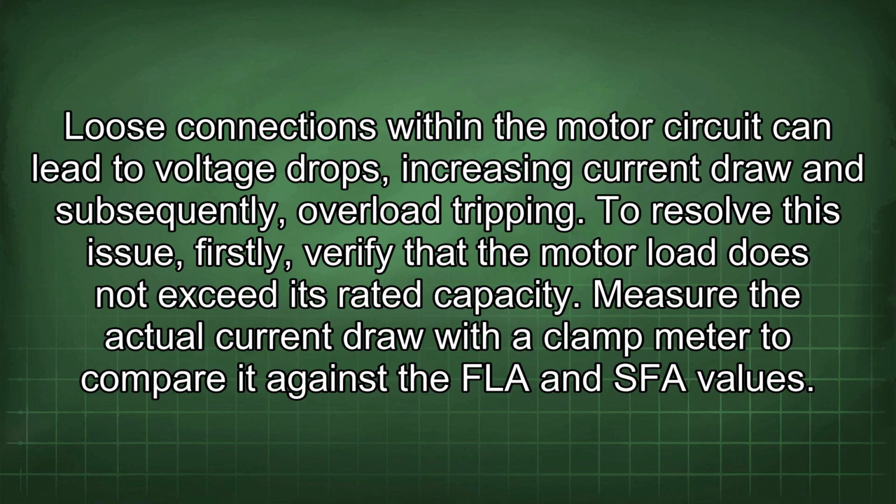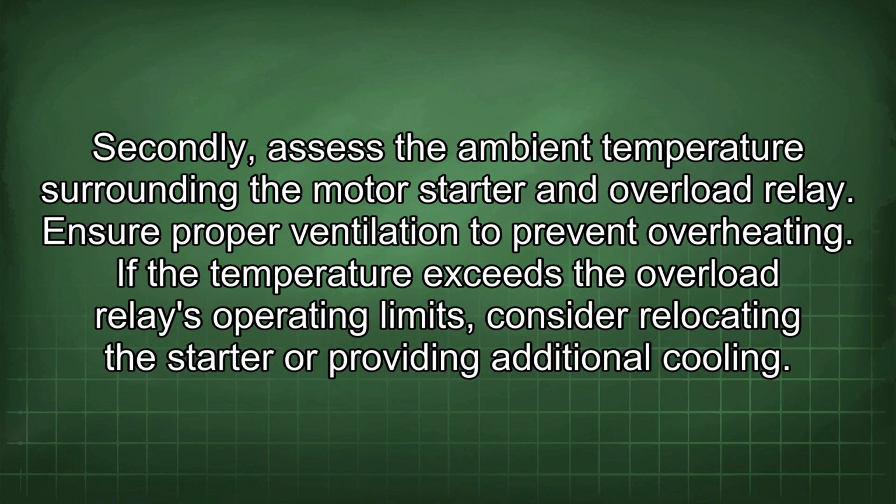To resolve this issue, firstly verify that the motor load does not exceed its rated capacity. Measure the actual current draw with a clamp meter to compare it against the FLA and SFA values. Secondly, assess the ambient temperature surrounding the motor starter and overload relay. Ensure proper ventilation to prevent overheating. If the temperature exceeds the overload relay's operating limit, consider relocating the starter or providing additional cooling.